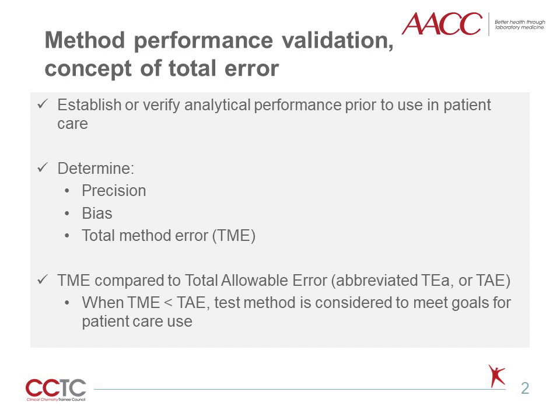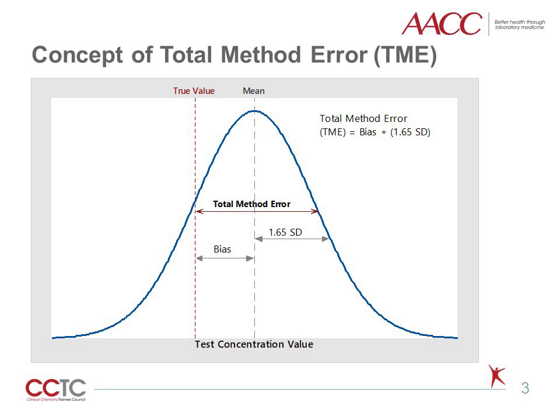When total method error is less than total allowable error, the new test method is usually considered to have met the necessary requirements for patient care use. TME is calculated from bias and standard deviation values obtained from method comparison experiments. The figure shown illustrates a positive bias with the new test method as compared to the true value established by a reference standard or other comparative method. Imprecision follows a Gaussian distribution, calculated using a Z value at the desired probability level. The traditional calculation is TME equals bias plus 1.65 times standard deviation.